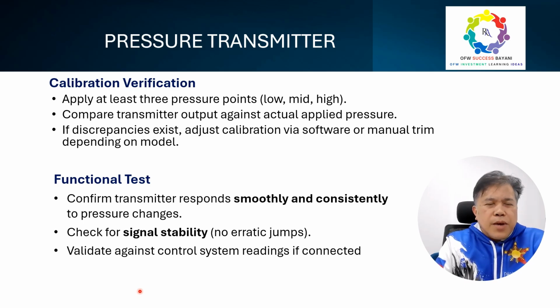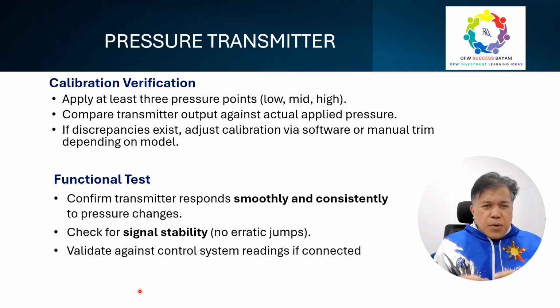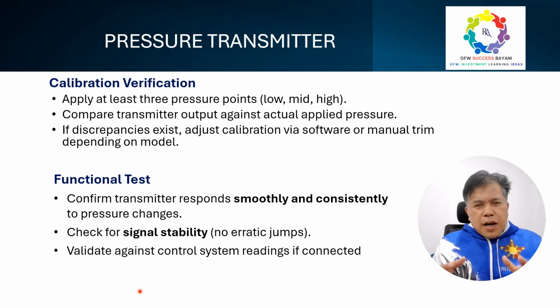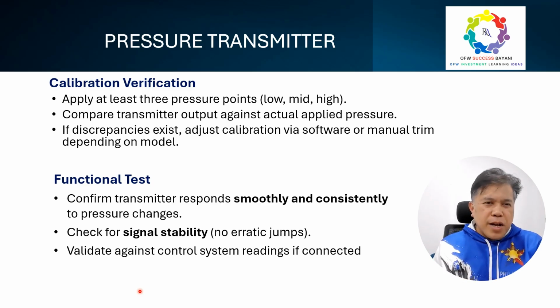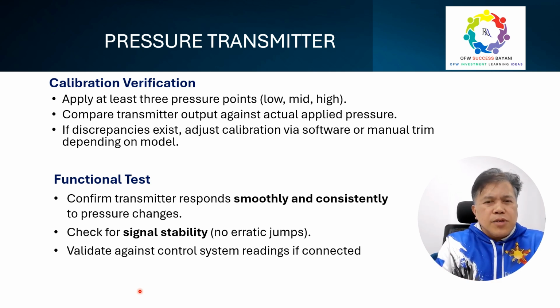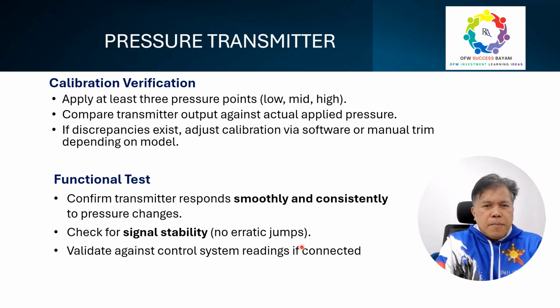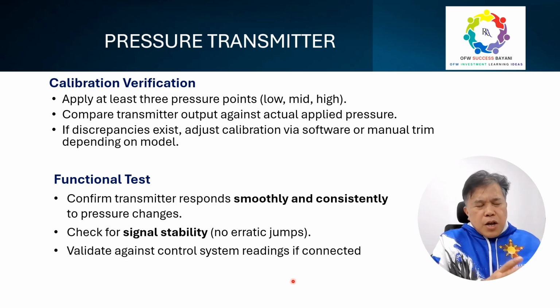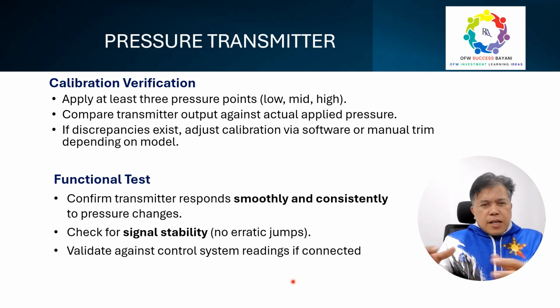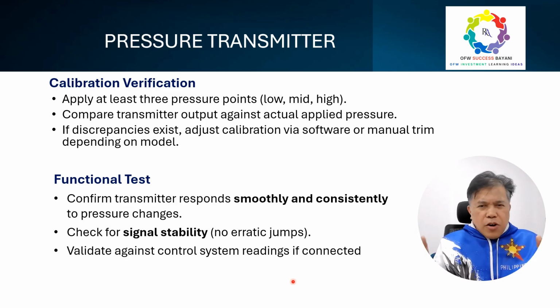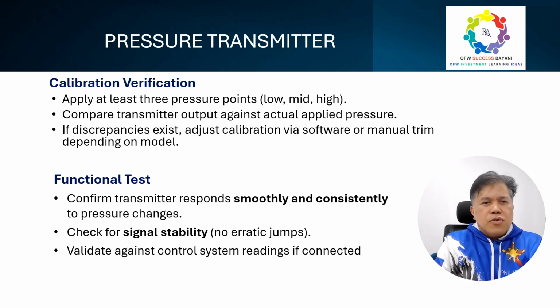So, the functional test. After all the installation inspections and pre-commissioning are done, we now do the functional test. The functional test comes from the commissioning team; they do the functional testing. Functional testing confirms the transmitter responds smoothly and consistently to pressure changes. Check signal stability with no erratic jumps, and validate against the control system reading. That's part of our functional testing. With the vendors, we have a program and we check our transmitters, where the signal is applicable, including interfacing with all of the systems and integration activities. So that's the whole process for our pressure transmitter: checklist, checking, verification, calibration, testing, etc.